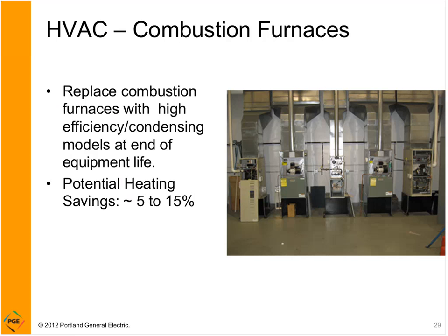So there's also a lot of combustion furnaces out there in commercial buildings, maybe residential size, but burning either natural gas or oil. Replacing these furnaces with high efficiency condensing models at end of equipment life is a good opportunity when you hit that point. Maybe the heat exchanger fails and the unit's 20 years old. You can go with standard efficiency, or you can go with 90+% efficient for gas, for example, even up to 95%. So a pretty big jump, maybe 5 to 15% savings over the older unit or code.